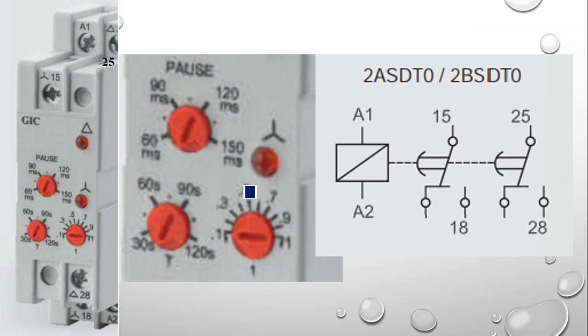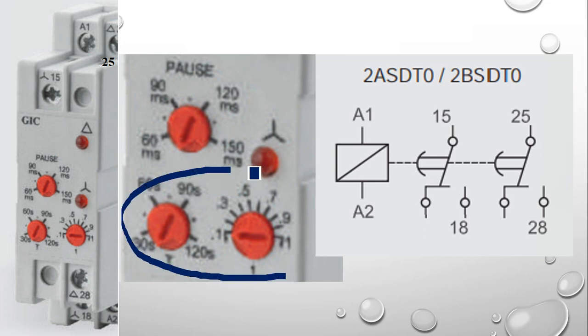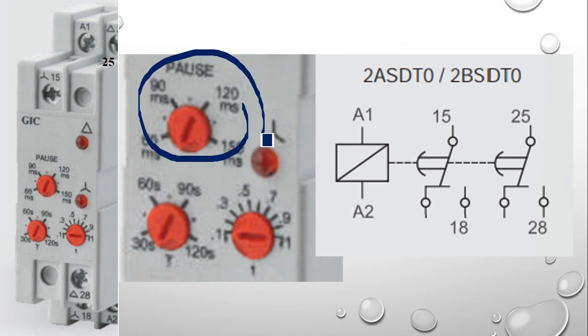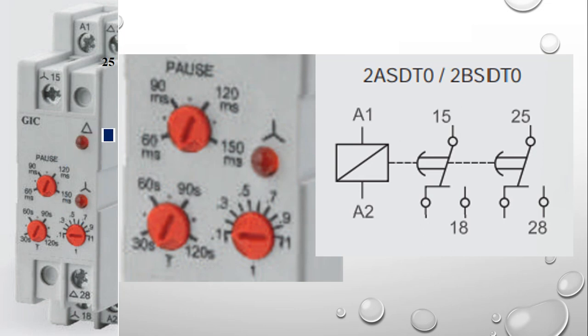For the minimum time, setting T to 30 seconds and t to 0.1 gives 3 seconds — the minimum timing for this relay. There is also a pause timing setting at the top for the time delay between star and delta changeover: options are 60 ms, 90 ms, 120 ms, or 150 ms. The front panel also has star and delta indication LEDs — the star LED lights when running in star, and the delta LED lights when running in delta.